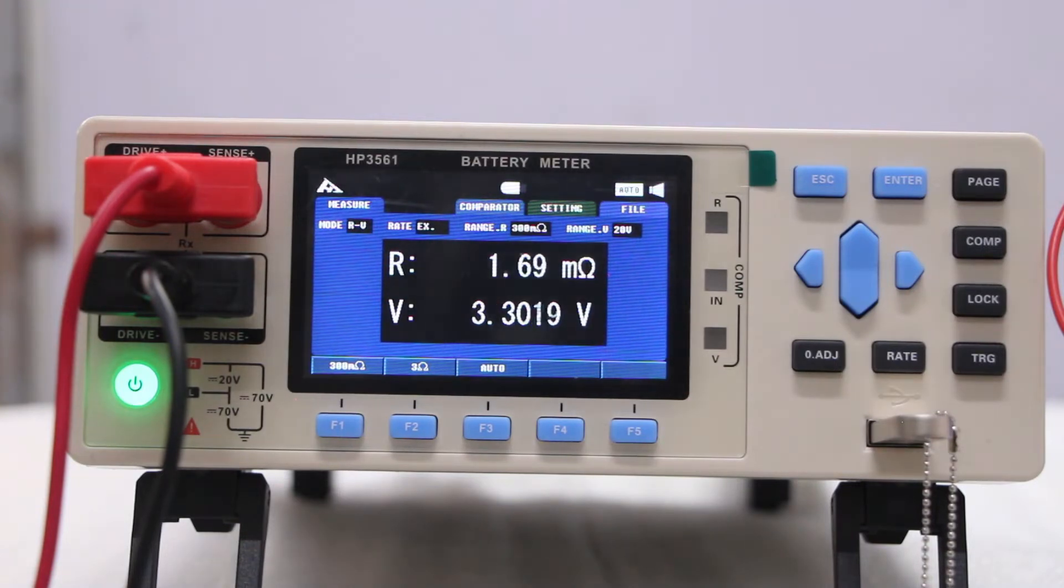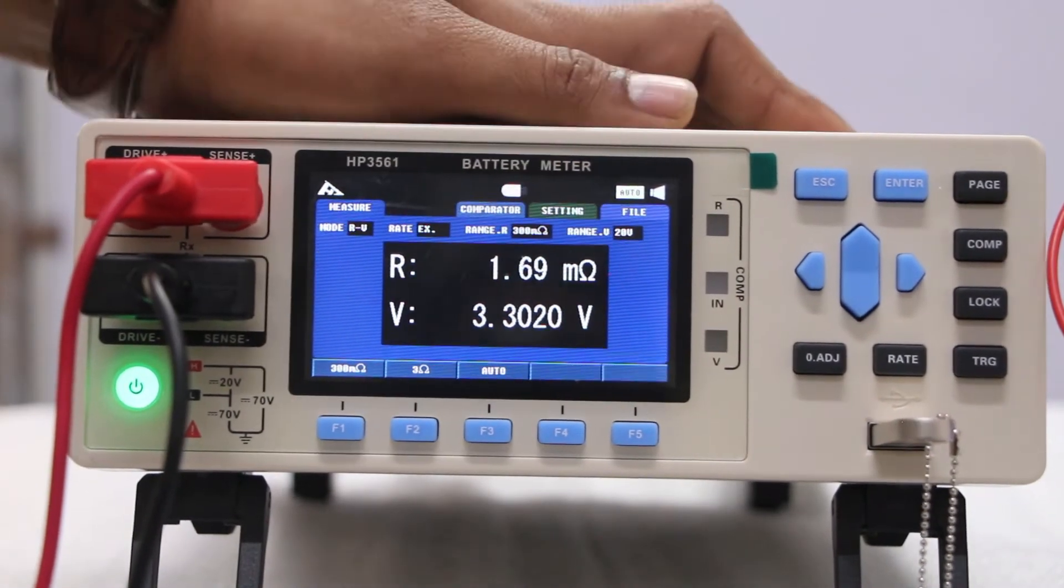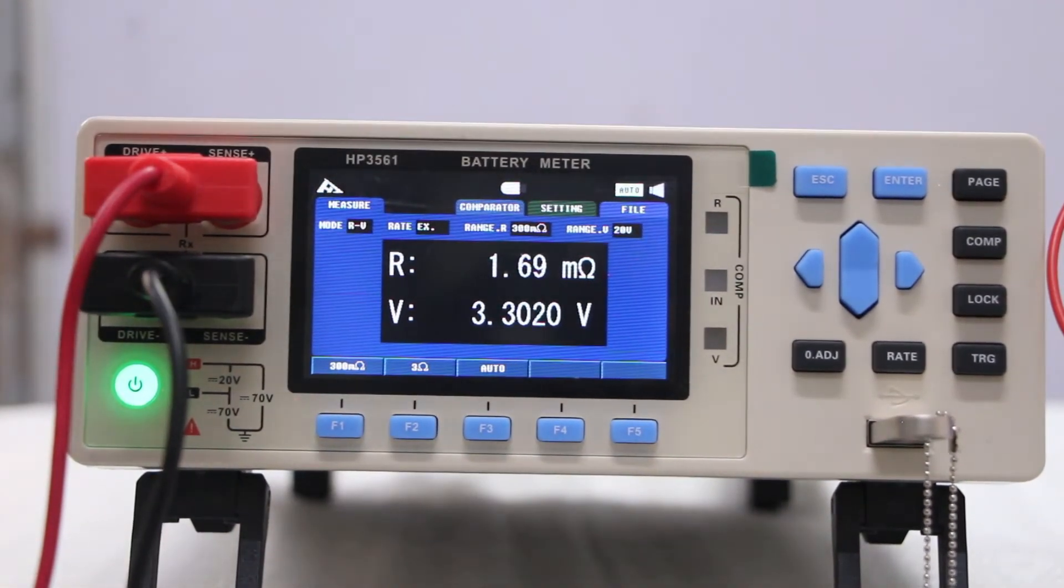In comparator you basically program within a range like we set a range according to your requirements, your battery or cell should be placed within the range. If it will be out of range, your comparator button result will be not good. By using this, you can also compare or sort your cell on the basis of IR or voltage level. Lock is for just locking the screen purpose.